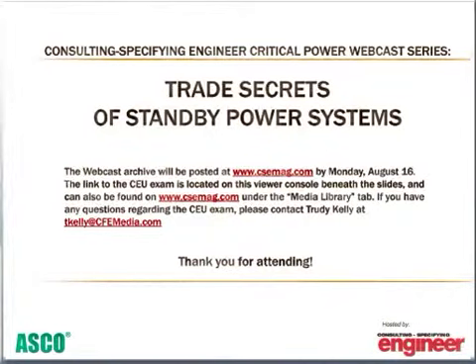Okay, good. Keith, the next question is from Alan Stevens of Siska-Hennessy, saying even though you are assuming 0.07 gallons per kilowatt hour fuel consumption, what value are you looking for as a real fuel flow from and to the generator from the day tank to address fuel injection pump cooling and the like? Well, that's a very specific question that you'd have to look at on a specific project. But the actual burn of a generator at full load, based on large generators that we see in mission-critical facilities, is about 0.07 gallons per kW per hour. So his question is pretty specific, and I wouldn't be able to provide just a general answer to that.